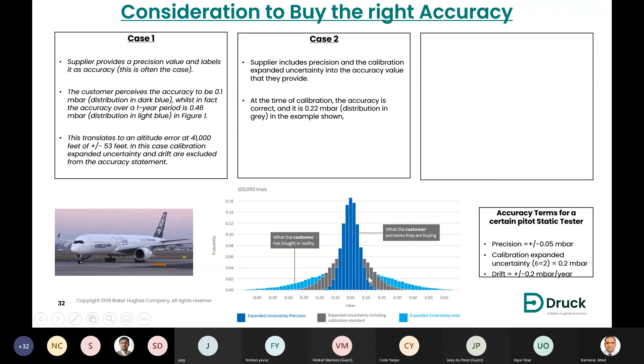But again, over 1 year, we will have a drift of 0.2 millibar per year, which will total 0.46 millibar, which is in the light blue. In this case, the drift is excluded from the accuracy statement. So the error would be 0.22 plus 0.2. This will be more than the label claimed in the datasheet of this tester. If you include all sources of errors in the accuracy term, but you do not mention how long you guarantee these specs, or what the drift is over 1 year, 18 months, then you leave us in the dark.